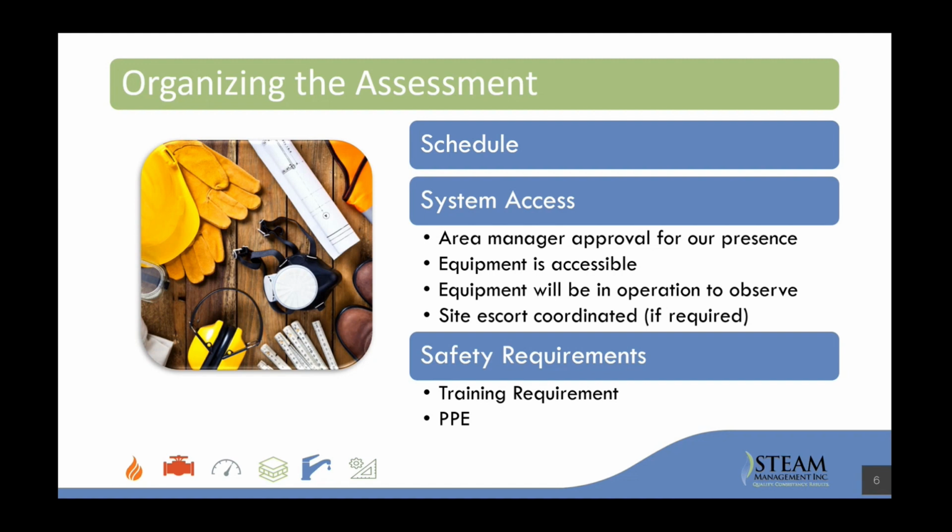And then what are your safety requirements? What is the training required, and what is the PPE required? Standard PPE is boots, hard hat, glasses, hearing protection. But there are other things different sites will require, like gloves or long sleeves. Sometimes you need special boots like metatarsal protection. Sometimes you need double hearing protection, non-static clothes.